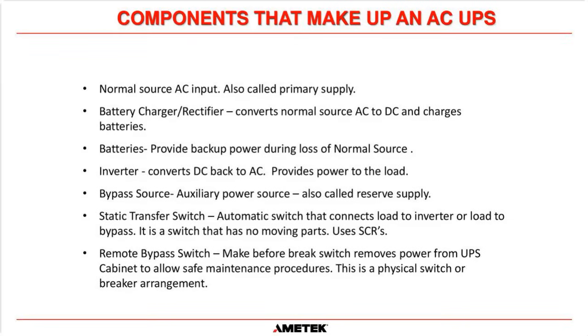And then the last thing that we're going to discuss is the remote bypass switch, which is a make before break mechanical switch that removes power from the UPS cabinet to allow safe maintenance. And it's a physical switch, or in some circumstances, it could be a breaker arrangement. Okay.